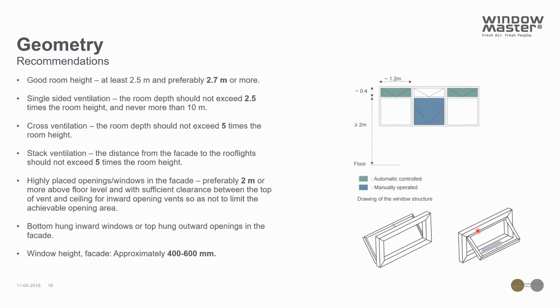For the windows themselves, we prefer and recommend placing them at two meters or more above the floor level. We recommend a window height of approximately 400 to 600 millimeters. They should not really be below 400 millimeters, and they can of course be above 600 millimeters but this will make the design more challenging — for example in relation to draft problems.